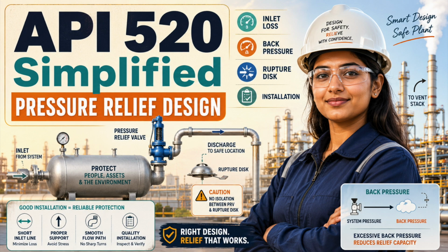You begin with the credible scenario, you determine the correct relieving load, you size at actual relieving conditions. You select the device for the real fluid phase, operating ratio, back pressure, temperature, and service quality. You control inlet pressure loss. You engineer the discharge path. You check reaction forces, materials, drainage, vents, isolation, and maintainability. The relief device is only one component in that chain.